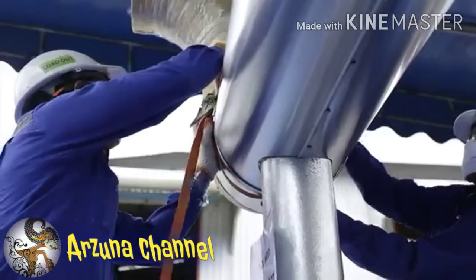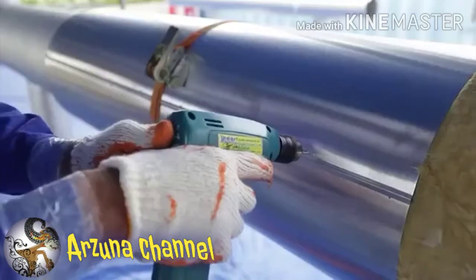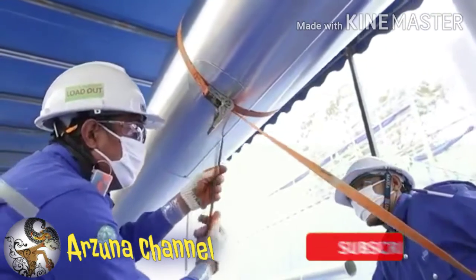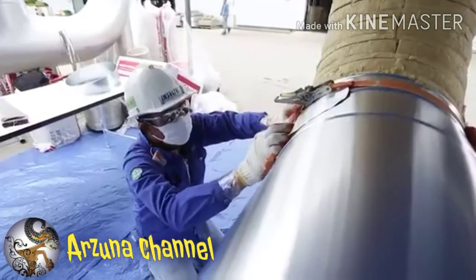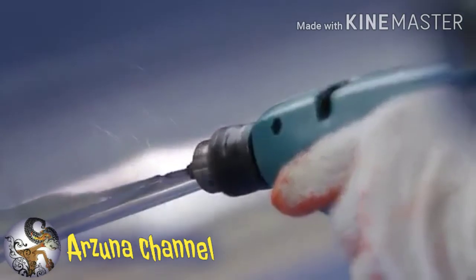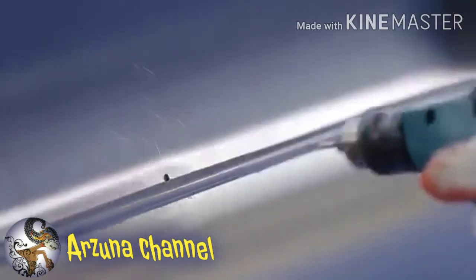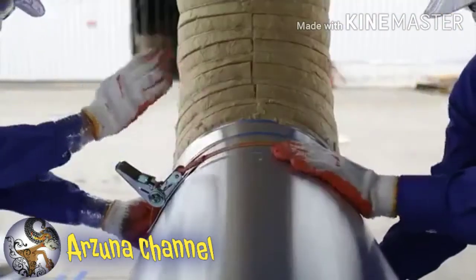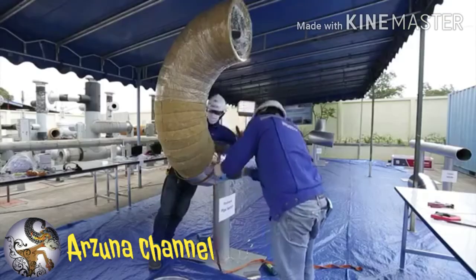Fasten sheet cladding with sheet metal screws or blind rivets at 150 mm center to center. We do not recommend using aluminum screws. Before fastening the cladding with screws, tighten the cladding with a belt, and a fraction of cladding can be used to prevent scratches on the cladding from the belt. Once cladding is secured in the horizontal part, cladding can be installed on the elbow from the bottom to the top one by one.